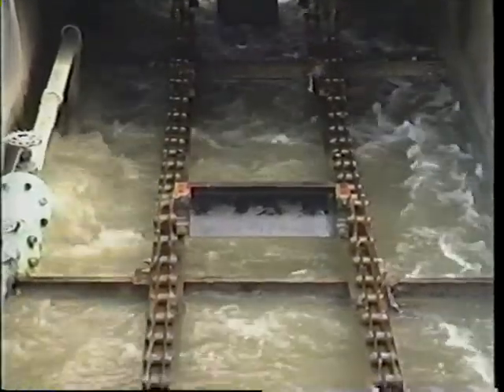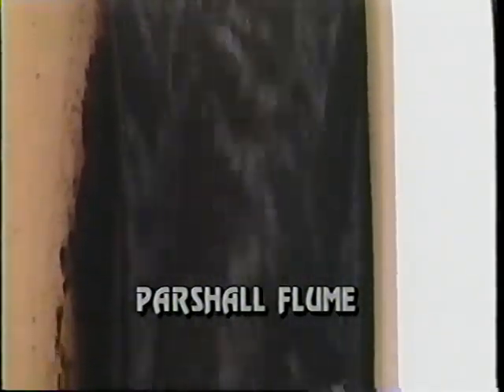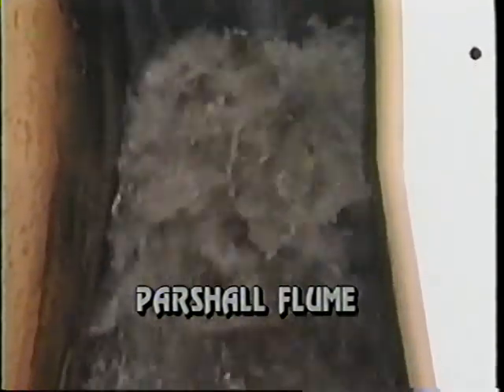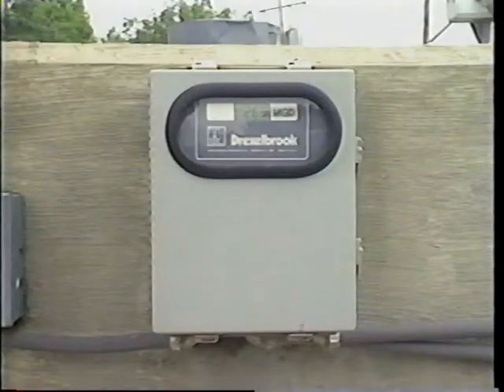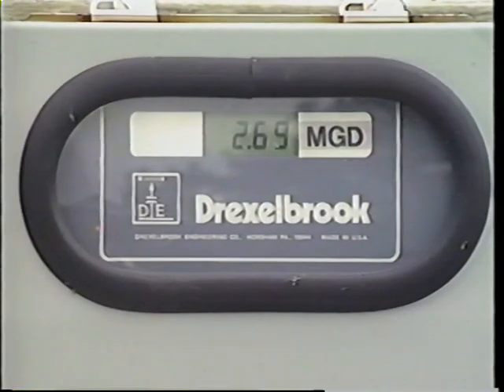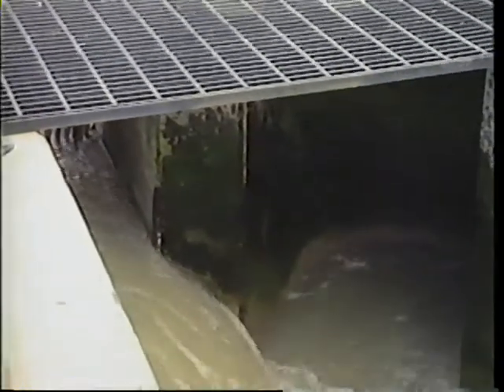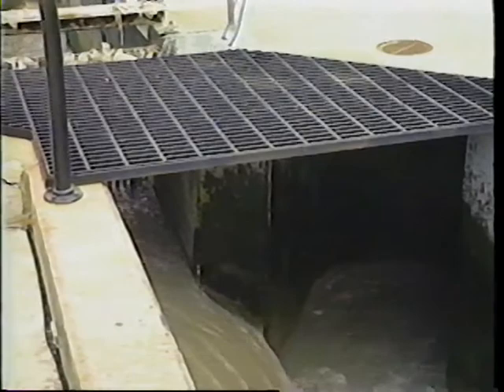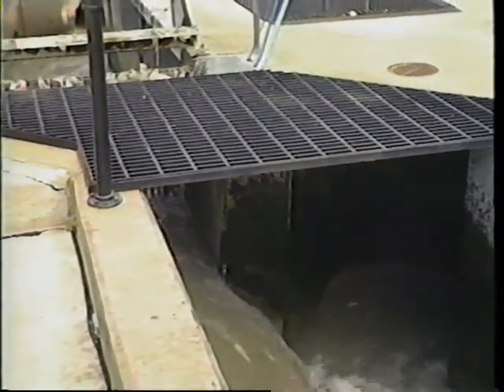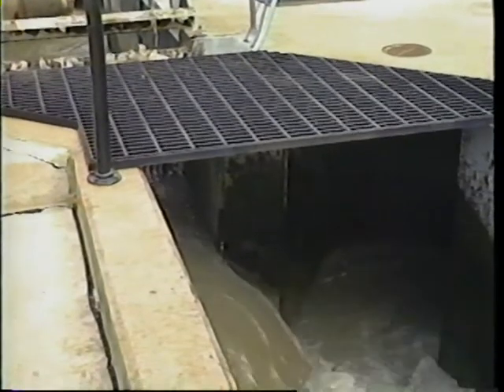Before treatment begins, it is necessary to know the quantity of wastewater flow so that pumping rates, aeration rates, or other adjustments can be made in the plant. The most commonly used primary flow measuring device is a Parshall flume. It's a kind of narrow channel which permits the quantity of flow to be determined by measuring the depth of the wastewater in the flume with some kind of measuring and recording device. One reason for the popularity of the Parshall flume is its smooth construction, which inhibits wastewater particles from catching or accumulating at the inlet, thereby rendering a maintenance-free operation.